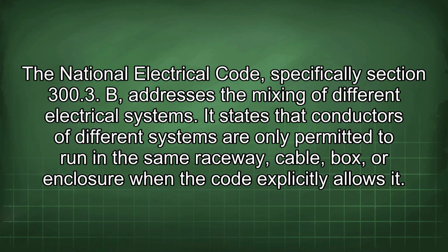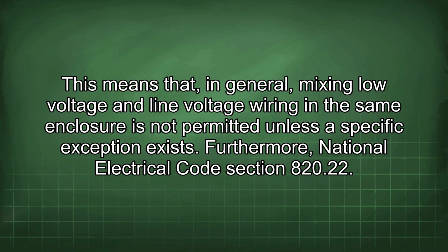The National Electrical Code, specifically Section 300.3(B), addresses the mixing of different electrical systems. It states that conductors of different systems are only permitted to run in the same raceway, cable, box, or enclosure when the code explicitly allows it.